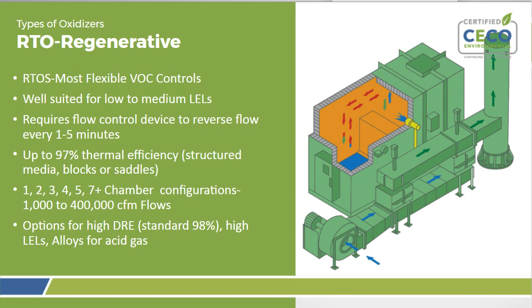and can be designed to accommodate very high LEL, think 30% LEL. If you know what LEL means, I don't know if we explained that earlier, lower explosive limit. It's essentially an indicator of the concentration of the VOCs that you have in your stream. So 100% LEL would mean that you're at the point at which an explosion, auto-ignition, would occur. So typically you need to stay below 50% for any thermal oxidizer. And there are many options for these that we'll go into as well. But first I want to talk a little more about just how the RTO works.